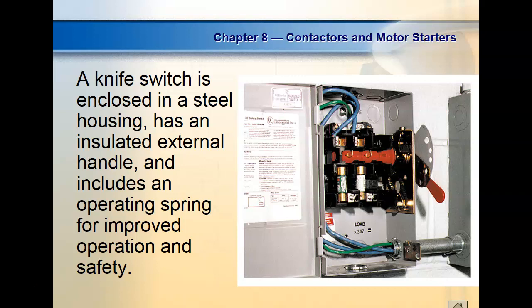These are spring loaded, so if you get the handle down to a certain spot, it gets past the plateau and it goes up. Awesome. Close it does the same way. It's got a little angle in there. Once you get past this trough and go over the other side, it pops up. Awesome. And normally they're sealed in a box, and the box has got a key. And then we have lockouts over here that are available to lock it out, right?